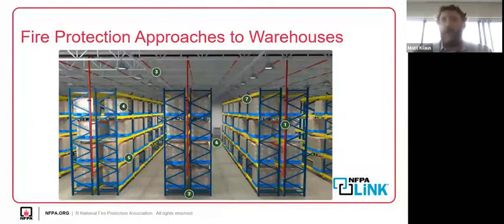Storage height matters too. Depending on how high we store goods, the fire grows vertically, and every rack tier we add can make that fire a lot more intense. We need to manage our storage heights relative to the ceiling and sprinklers, making sure we're not putting cardboard boxes an inch away from the sprinkler deflector.